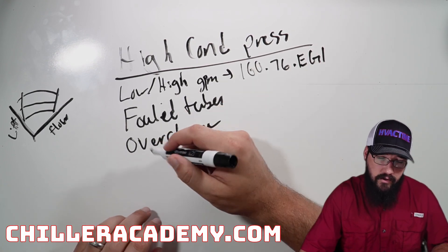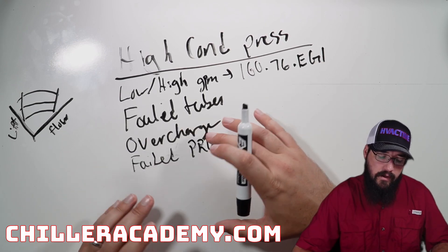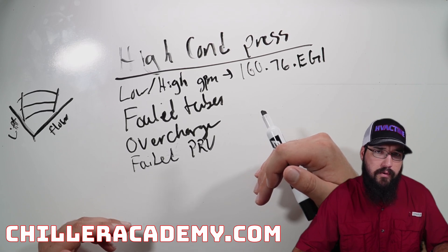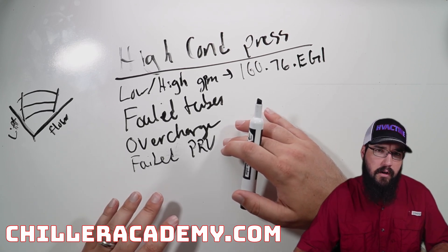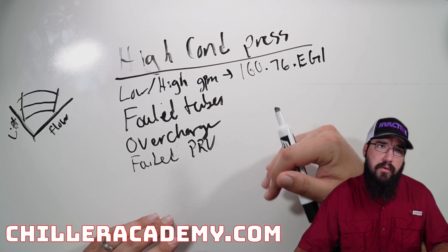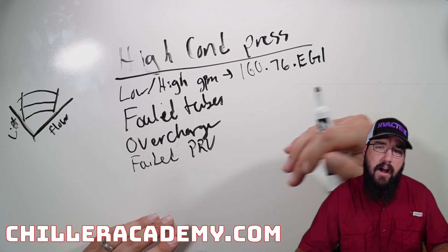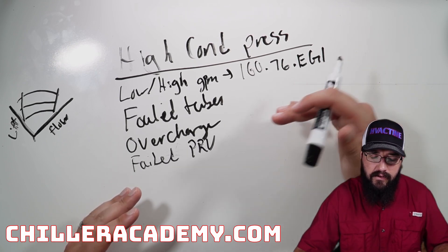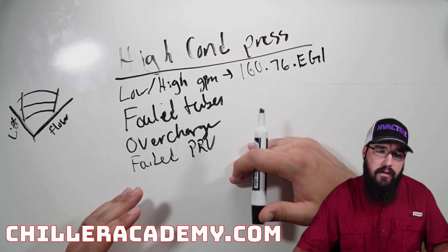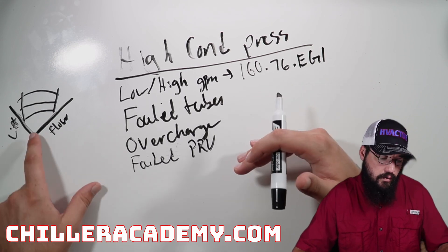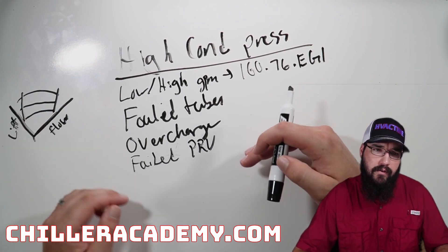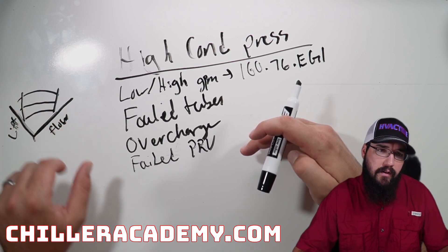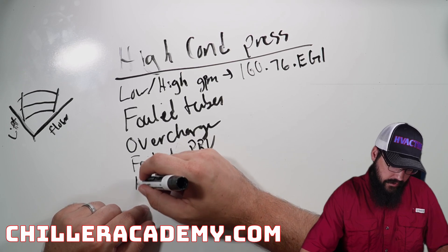If the condenser liquid level is at the correct set point but you've got a really high evaporator level in the sight glass, there's a good possibility you could be dealing with overcharge, and you'd likely see elevated evaporator pressure. If there's no overcharge, then a failed PRV is our next culprit. With a failed PRV, we either aren't able to choke the refrigerant off properly — probably the more common failure — which is going to force us to run a higher head pressure and higher lift. We won't be able to unload the way we need to in order to get back below that surge line on the graph.